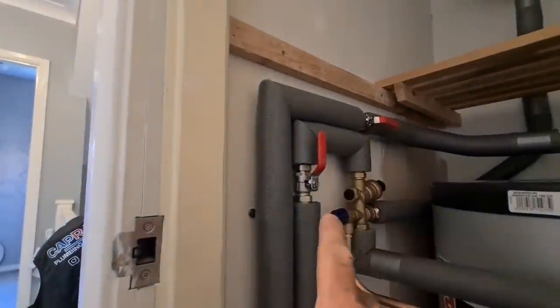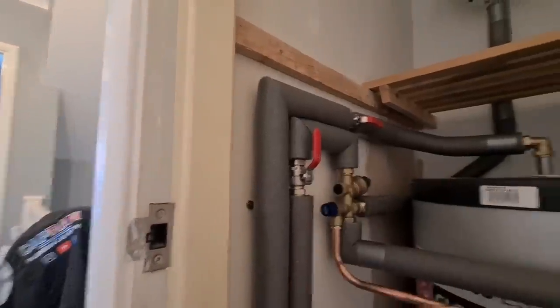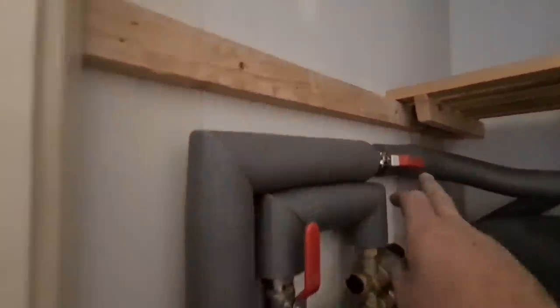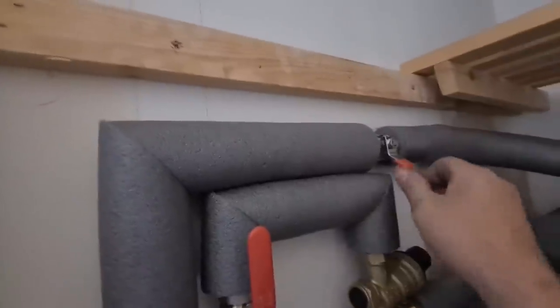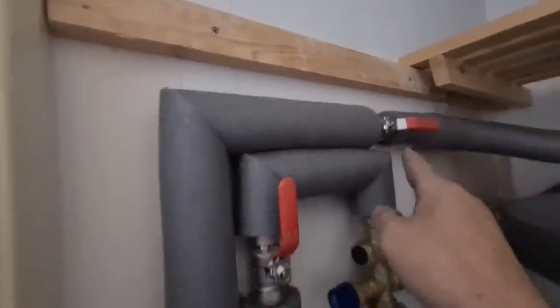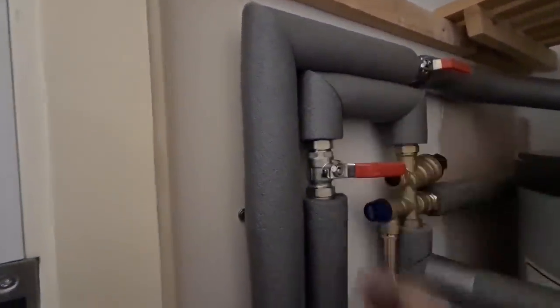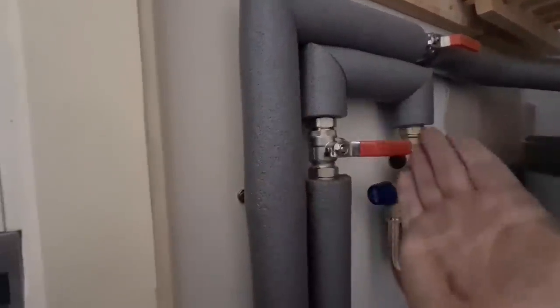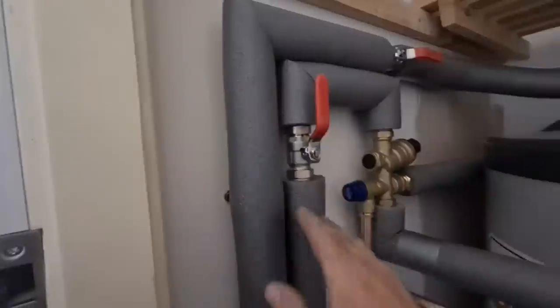So I've got a local isolation valve for my cold main. Hot's isolatable as well there. Don't panic, guys, before I start whinging, there's a valve there. I always like to do that, it drops the pressure straight away. And when you're installing lever valves, they need to fall to off. You'd never put them to fall to open, reason being, if something got knocked and knocked it open, that's not what's meant to be, so always fall to off.